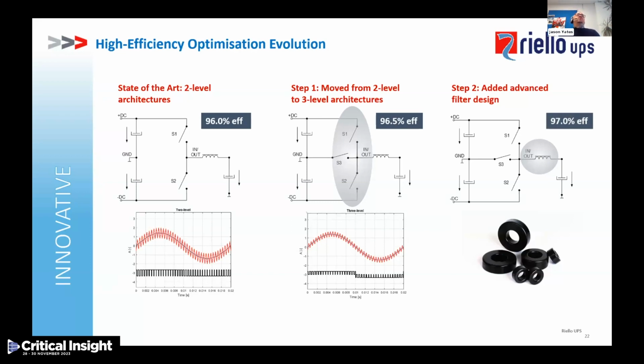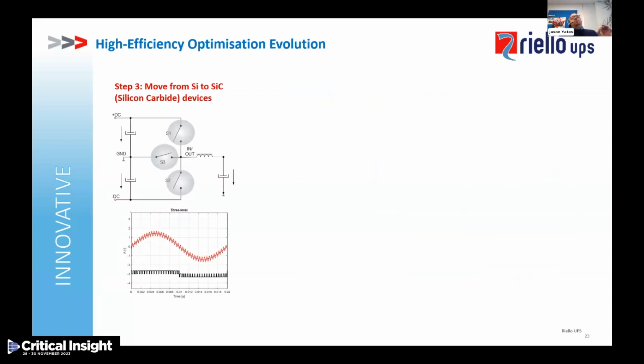Now, the very latest change to UPS design, recently introduced, and this is all primarily driven by the EV market, is the move from traditional silicon components over to silicon carbide components. Again, same design, but instead of using a traditional IGBT, we're now using a silicon carbide MOSFET device, which again is very commonly used in the EV markets. The benefit of silicon carbide is that it can produce efficiency levels up to 98.1%. In fact, during testing at times, we've pushed even 98.2%. So how is that being achieved?